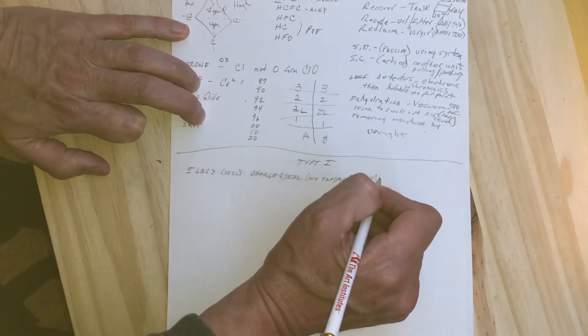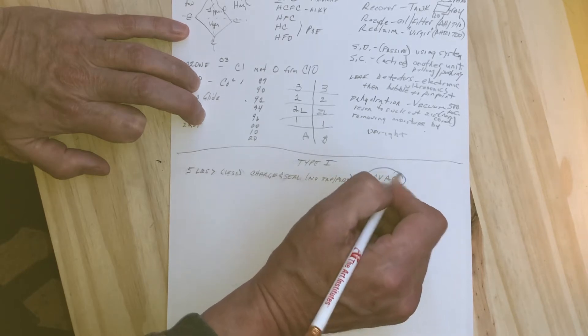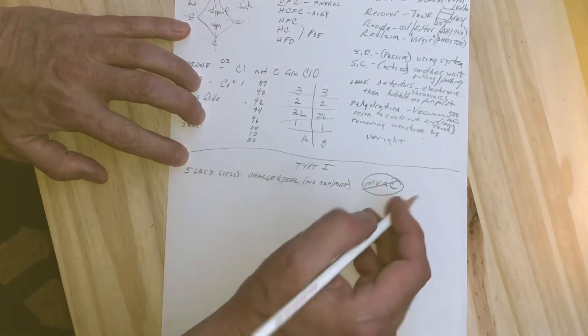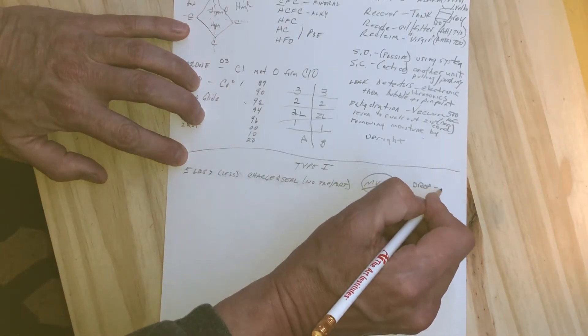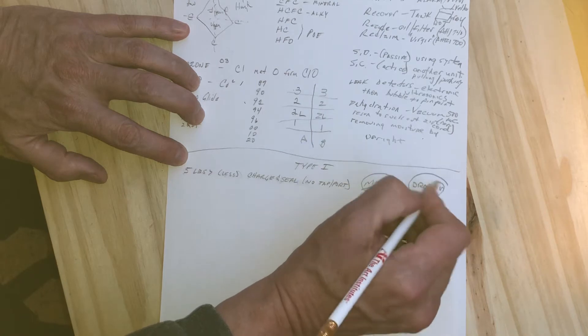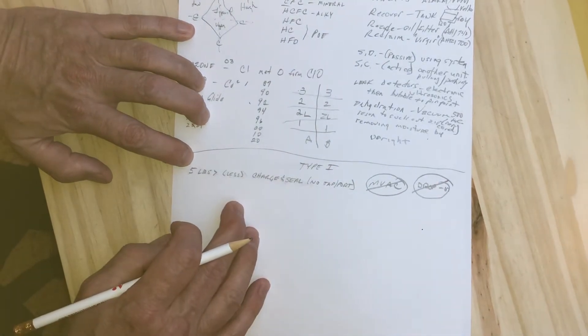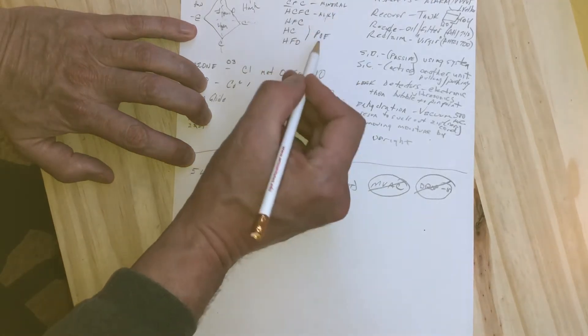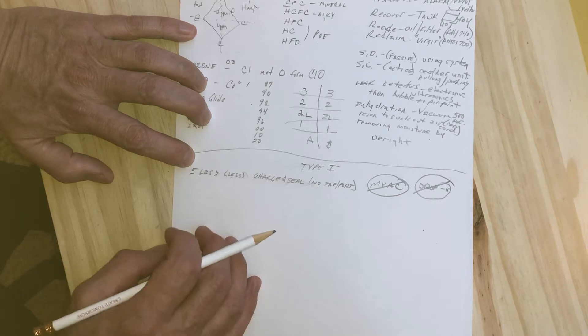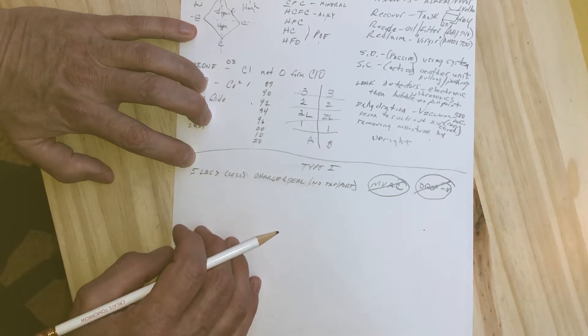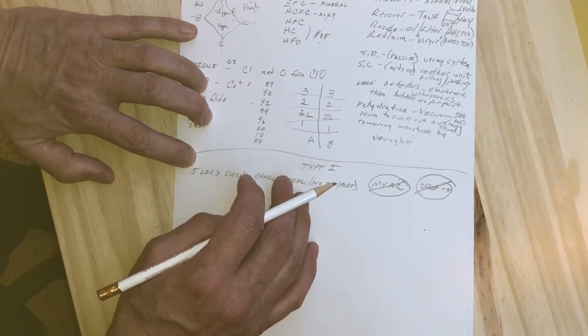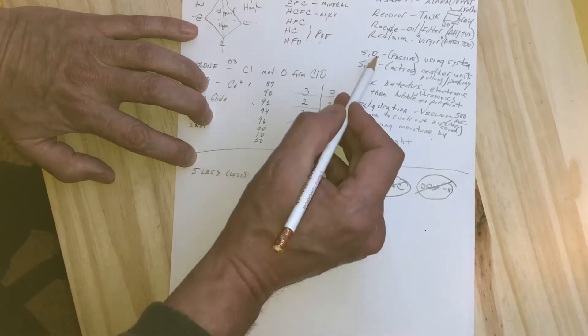These are not MVAC systems, motor vehicle air conditioning systems, which is a different section. There's also no drop-in replacement for any of the refrigerants in Type 1 appliances because sometimes the oil will need to be swapped out, and that's a retrofit.